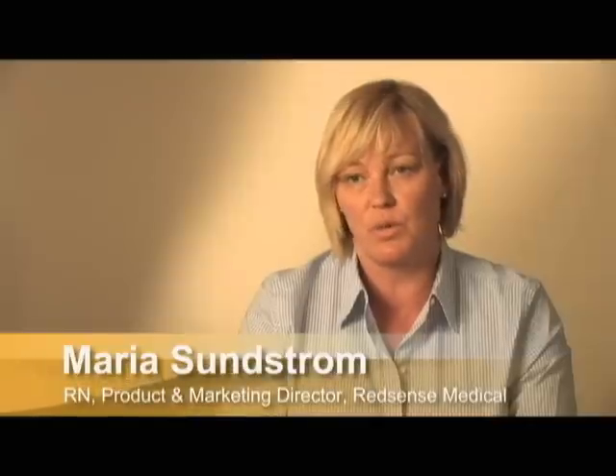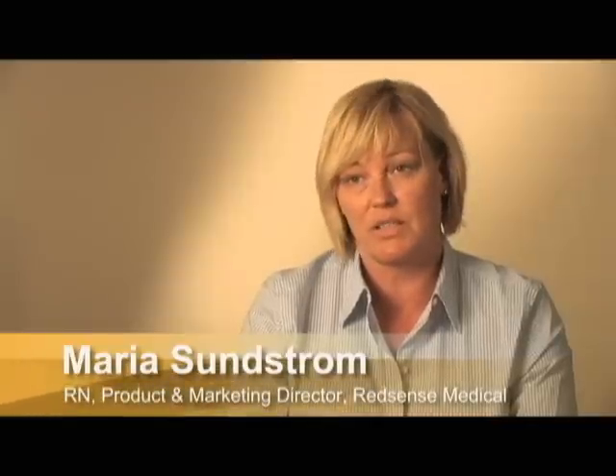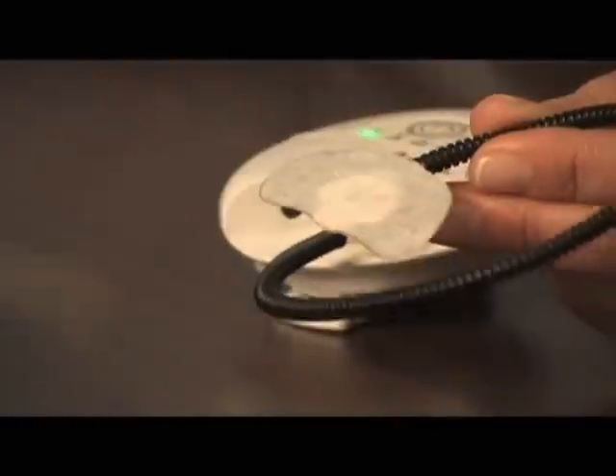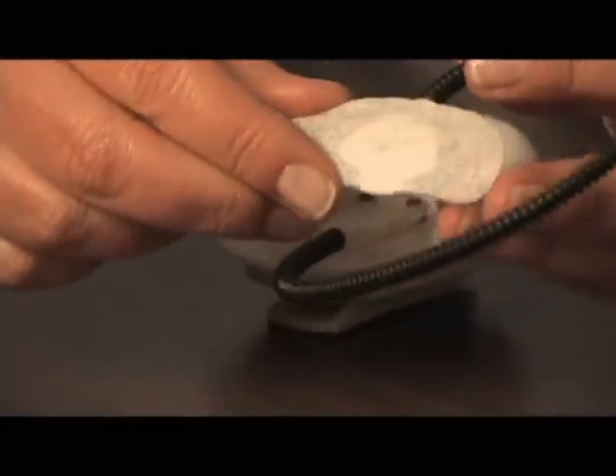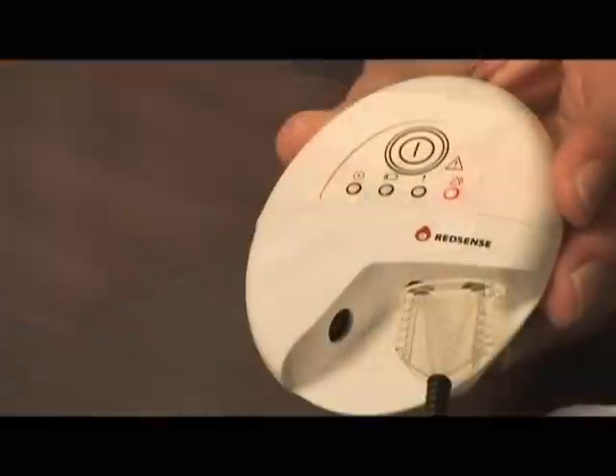Redsense is a blood detecting device using fiber optic technology. It consists of two parts, one alarm unit and one sensor patch. The alarm unit sends an infrared light through the optical fiber. When blood comes in contact with the optical fiber band at the tip of the sensor, it will trigger a visual and audible alarm.